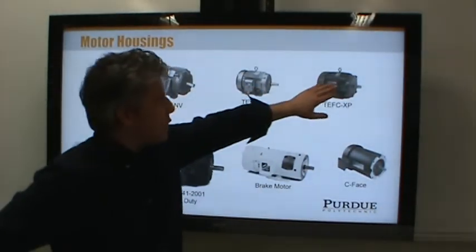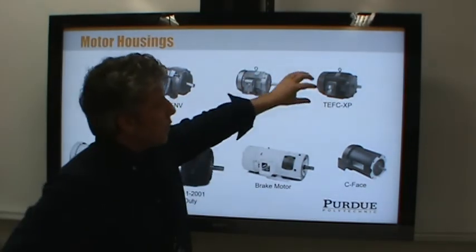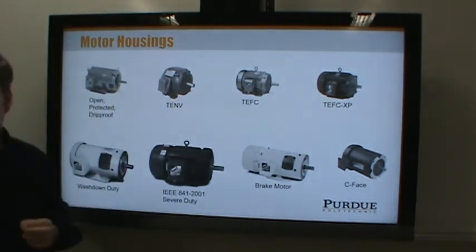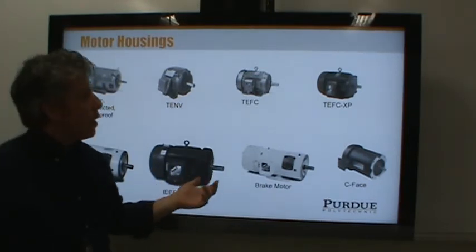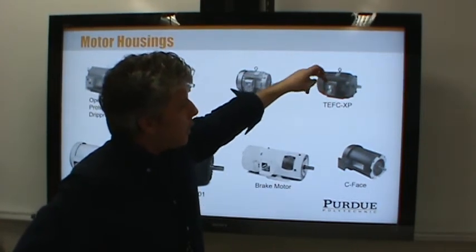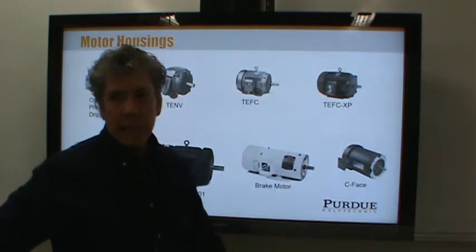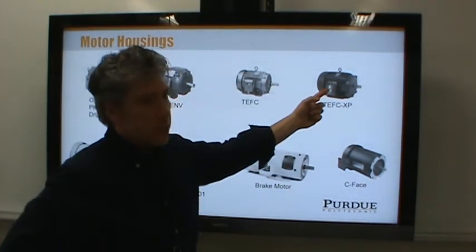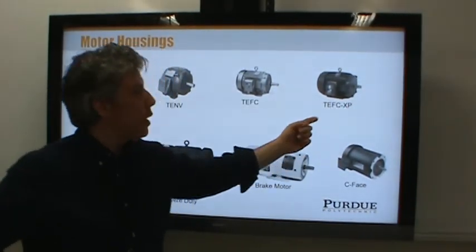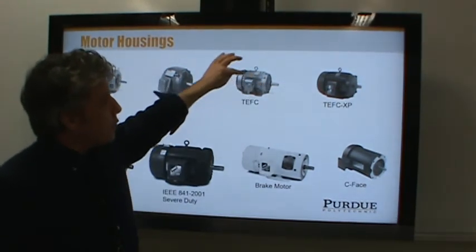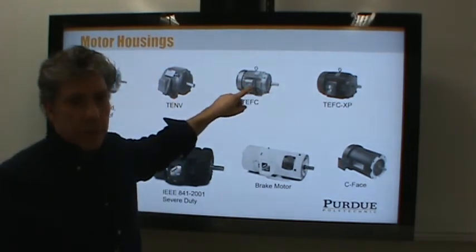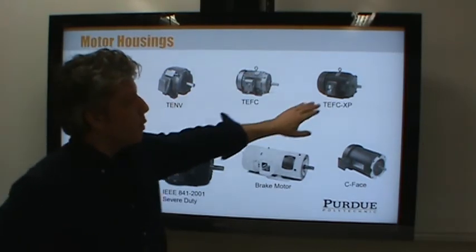The big difference between TEFC and explosion-proof motors is the sealing. Notice the junction boxes on the side — that's where you connect the wires. The explosion-proof motor has very good sealing around the housing so that gases can't pass through and any sparks inside cannot contact an explosive atmosphere. A standard TEFC won't have sparks from the windings since it's fully enclosed, but could spark at the electrical connections.